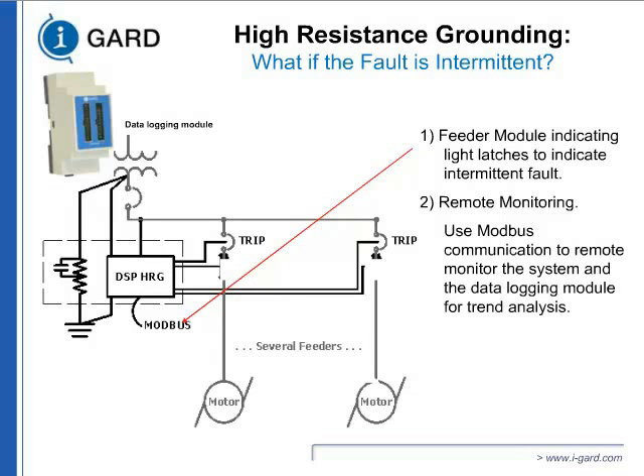Hey, the fault did happen. We need to take a planned outage and start checking. And all of this system can go now to data logging, so you have time and everything available. What if a second ground fault happens?